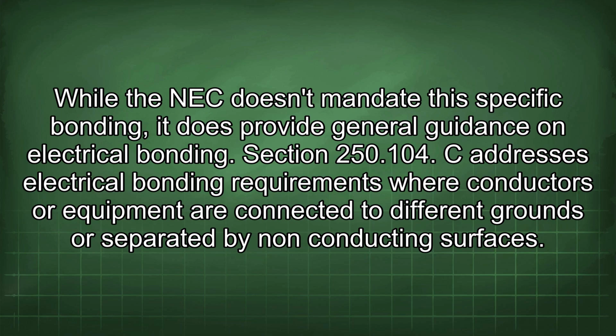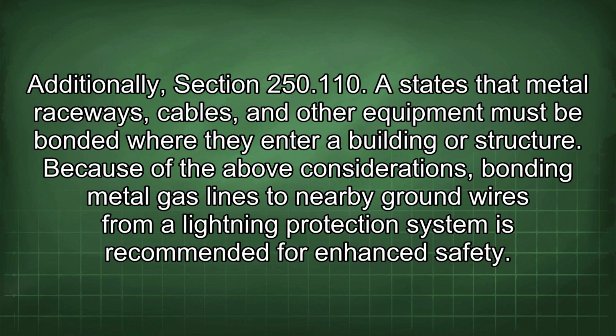Section 250.104(C) addresses electrical bonding requirements where conductors or equipment are connected to different grounds or separated by non-conducting surfaces. Additionally, Section 250.110 states that metal raceways, cables, and other equipment must be bonded where they enter a building or structure.